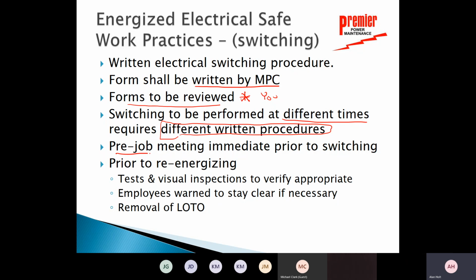Then there has to be a pre-job meeting immediately prior to the switching. We should attend that. We should have somebody attending that pre-job meeting for the switching. And then prior to re-energizing, there need to be tests and visual inspections to verify that everything's appropriately reconnected. Employees have to be warned to stay clear, and then the removal of lockout. And key is grounds and stingers, guys. We've got to make sure that all the grounds and stingers have been removed.